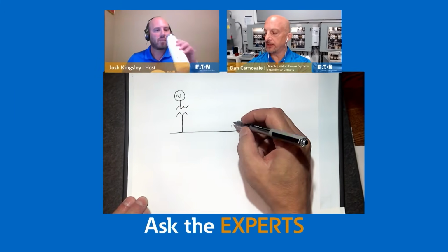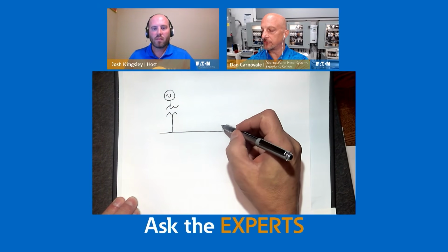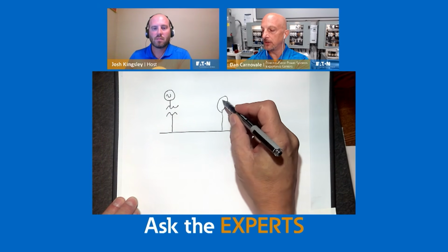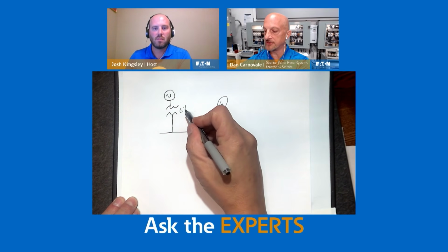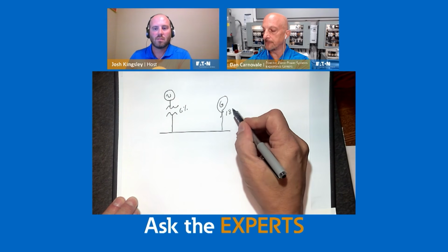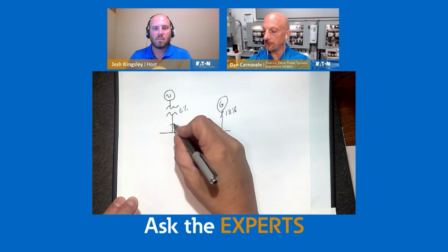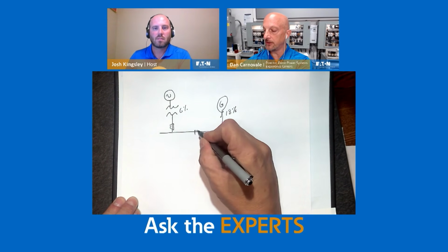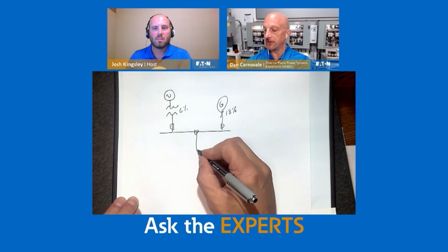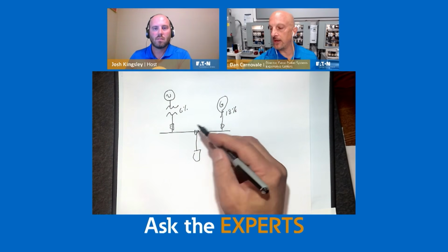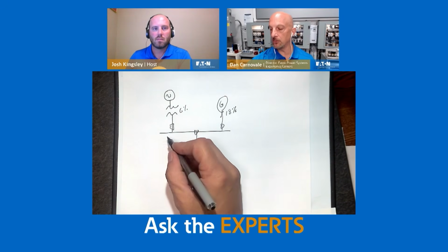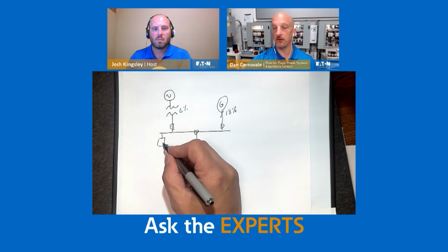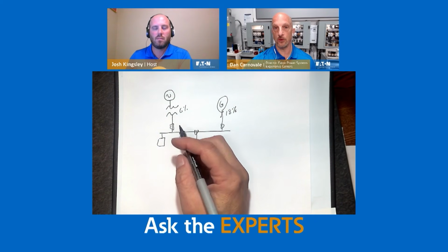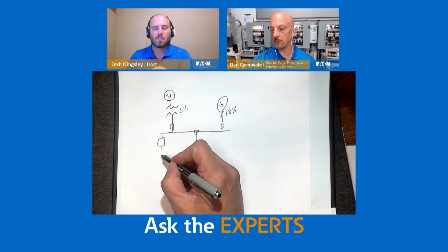Yeah, and what I run into a lot, actually, Josh, is if you do have your generator connected in here, and again, this would be some sort of transfer scheme. So I'll just draw it as if they're both connected in parallel, but you'd have a generator here. Again, this is, let's say, just simplified 6%, 18%. And then you have a transfer scheme with breakers or contactors or whatever. And then you feed your loads down here. So if you had no generator, but you added one later and you had a whole bunch of harmonic producing loads, and again, we're going to call harmonic producing loads kind of the new normal, anything electronic, but specific to today, we're talking about drives.